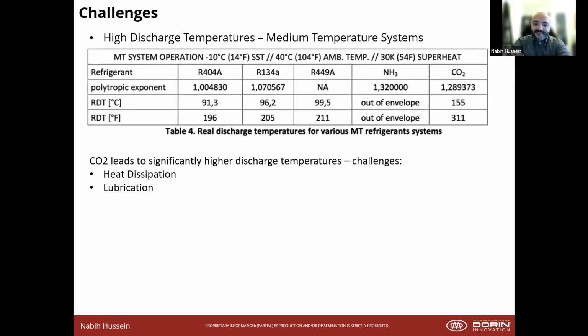High discharge temperatures is the next thing that is a consideration in the design of CO2 compressors. For HFCs, you're looking at 196 as a normal discharge temperature. And if you saw anything higher than that, you would think something was going wrong. But with CO2 standard operation, you're looking at around 311 degrees Fahrenheit. The challenge that this poses is you have to figure out heat dissipation for the compressor, and you also need to figure out proper lubrication. So those are the two challenges we're going to focus on: design improvements to a compressor and validation for making a compressor work in a CO2 application.